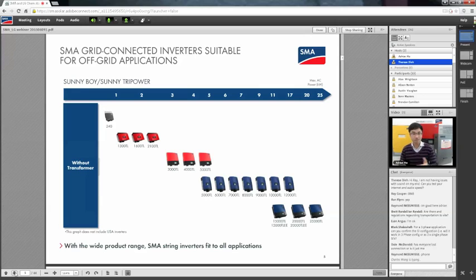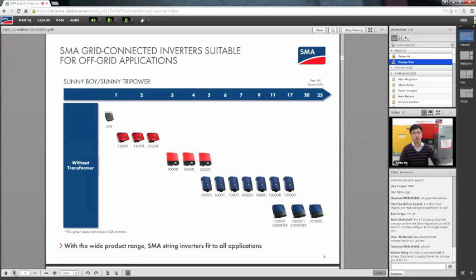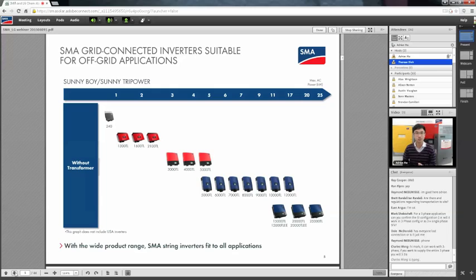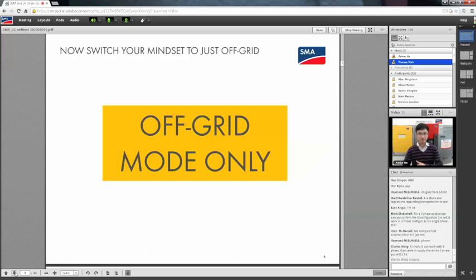At the moment, even though you have AC voltage and frequency, you still need some form of generation source. So of course, using quality products, we recommend the SMA Sunny Boy, single phase of course. You can also attach a three-phase system with the Tripower. At the moment, the system is not compatible with the micro SP240, so just stay focused with the string inverters. From now onwards, off-grid mode, until I tell you to go to on-grid mode.